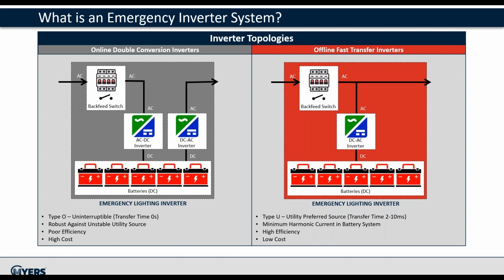Offline fast transfer systems have one power section that is used to charge the battery bank and supply the load during emergency. Offline fast transfer systems are the preferred choice for emergency lighting due to minimum transfer time, 2 to 10 milliseconds, which is well acceptable for lighting systems, minimum harmonic content, very high efficiency, and lower cost.